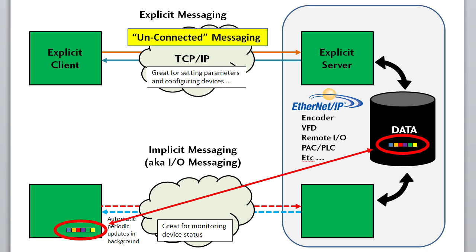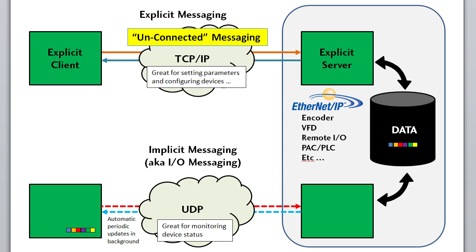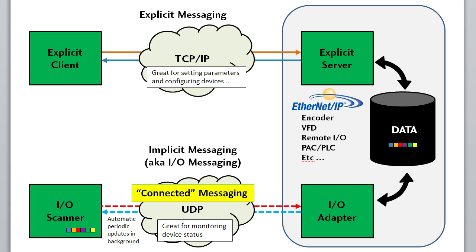This implicit messaging is done using UDP, and because this is different from the explicit nature of the client-server pair, we use different names for these. We have the implicit scanner — which we call the I/O scanner for short — and the I/O adapter. This is referred to as connected messaging, and the explicit approach is referred to as unconnected messaging.